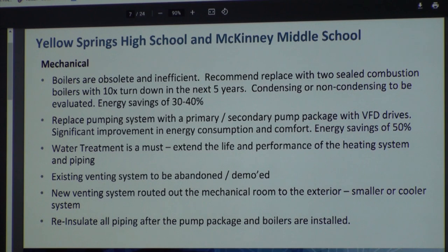Let's see, water, new venting system - and I'm going to talk about that. And then re-insulating the pipes - I think there's a lot of bare pipe. There's a lot of insulation that is loose, it's there but it's loose, it's come loose, and that's really not insulating the pipe. So I think at some point an insulation package is a good idea. Obviously, if you do a renovation, everything gets insulated. We now jacket everything because contractors climb around on that stuff, they step on the insulation and smash it. That doesn't work, so we've been more and more jacketing the pipe so it's a little more resilient. It's never going to be so good you can climb on it, and I did see some places where it looked like contractors were climbing on your insulation.